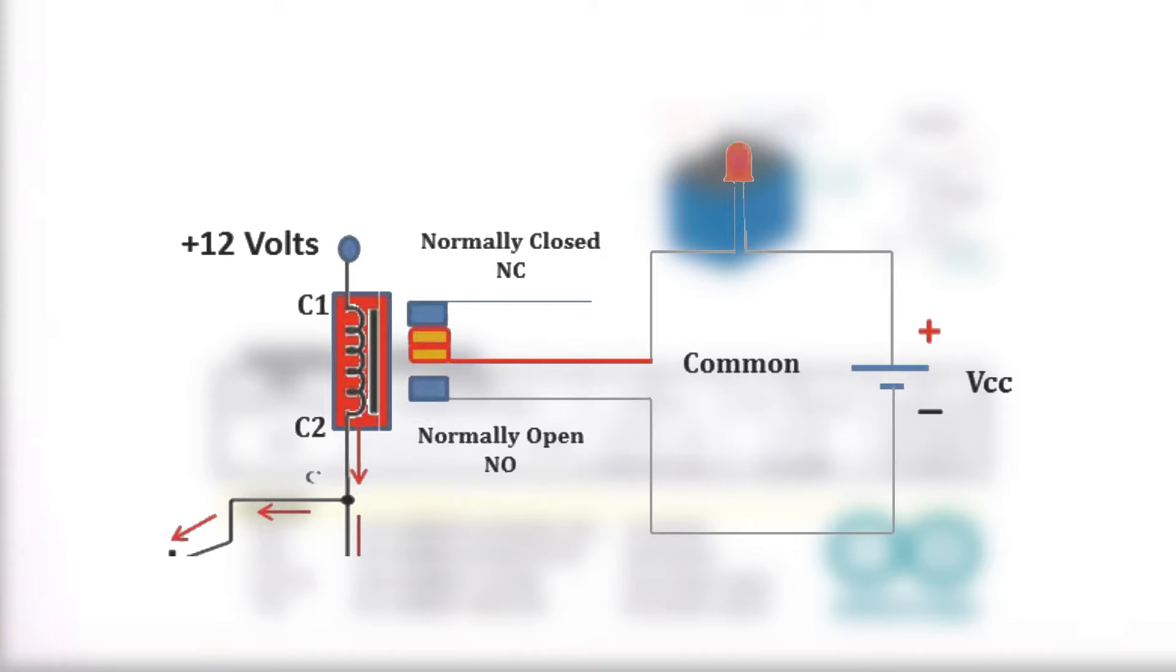When current flows to the coil of the relay, a magnetic field is created that causes the ferrous armature to move, either making or breaking the electric connections. When the electromagnet is energized, the normally open is the one which is on and the normally closed is the one which is off.